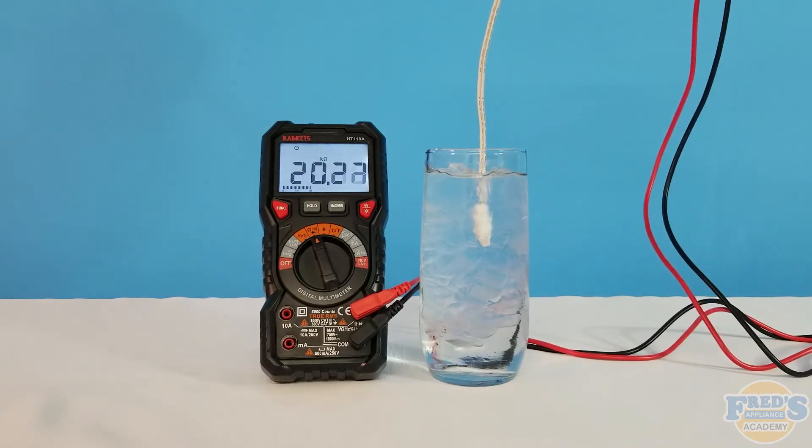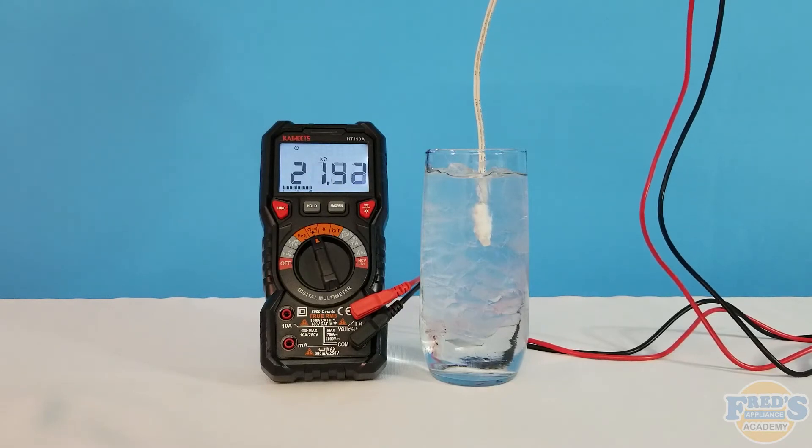It's important anytime you're testing a thermistor that you have a chart telling you what the resistance value of the thermistor should be at any given temperature.